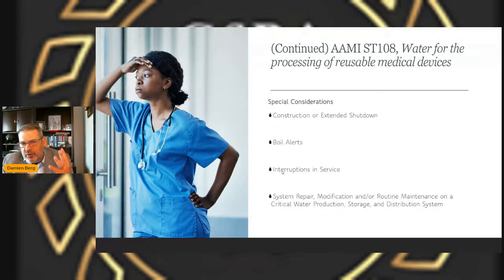And there are 4 main areas that are recommended. One is your sink, and there are 2 spots in the sink. You should know your tap water, your initial rinse, which does not need to be critical, but that will tell you what you're at. That's the stuff coming in from your central utility plant or your town or your city. So know what that is. You can get a sample of that, or your water company can, or your instrument or mechanical washer or repair company can. Your hospital needs to set up a policy on who tests, but get your initial rinse water. Then at your sink, you should have a final rinse water, and that should be critical, especially for your hand wash items or your eye instruments or things like that.